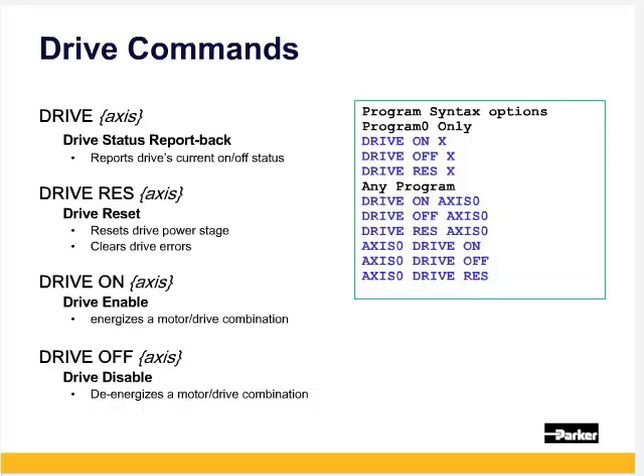Most drives have an enable input that must be enabled to power a motor. When the DRIVE ON command is set, the axis's enable output turns on enabling the drive. Its polarity of active high or active low is set in the drive configuration in the drive motor screen. The configuration wizard by default sets the enable drive IO bit, which activates these drive enable outputs. When doing a DRIVE ON, a REN command is automatically set, setting the commanded position to the actual encoder position. This prevents the possibility for abrupt motion to a distant commanded position.